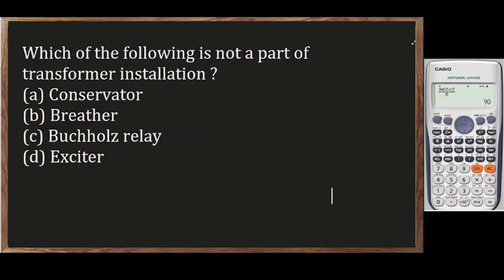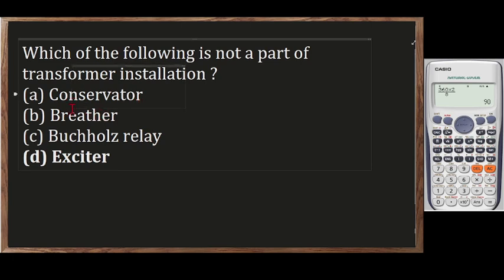Okay, next. Which of the following is not part of a transformer installation? So, is it a conservator, breather, buchholz relay, or exciter? Okay? The correct answer for this one is letter D, the exciter. So, exciter is used on a generator or an alternator. So, the breather, the conservator, and the buchholz relay are the common parts of a forced oil, air cooled, and water cooled type of transformer, no?